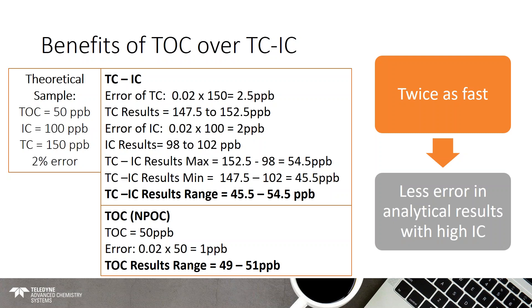Let's talk about the benefits of TOC over TC minus IC. EP 2.2.44 permits both TOC or TC minus IC. The Fusion is capable of doing either and has methods for both pre-programmed. I chose TOC for this study for two reasons: first, it's twice as fast — you're only taking one measurement instead of two. Second, it has less error in the analytical results, especially for samples that are high in inorganic carbon.